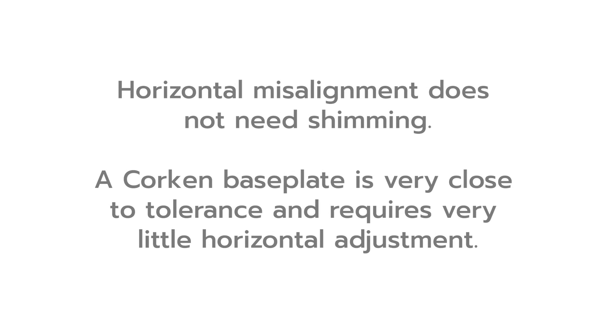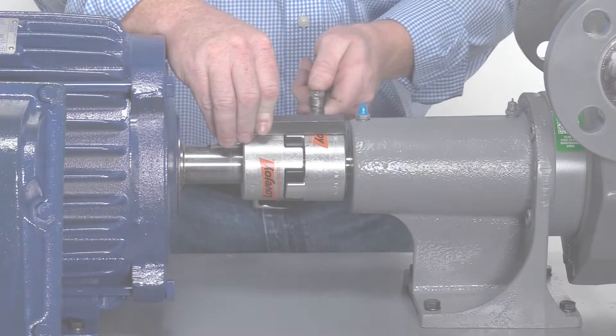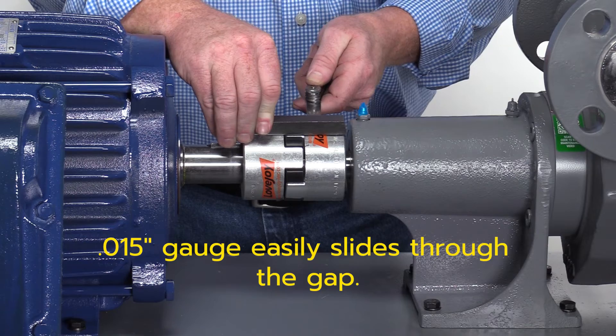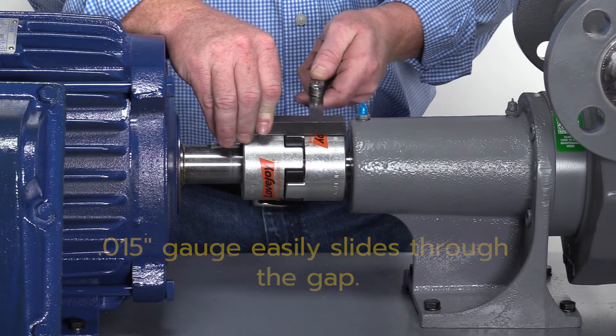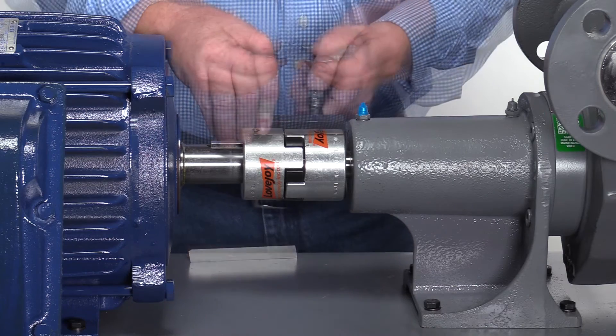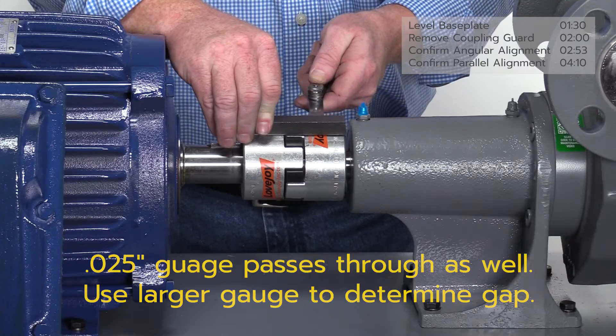Horizontal misalignment does not require shimming. A Corken supplied base plate is generally very close to tolerance and requires very little horizontal adjustment. Vertical misalignment requires shimming of either the pump or motor. In this example, the 15 thousandths gauge easily slides through the gap between the coupling and the straight edge. The coupling is out of tolerance and must be realigned. In this case, the pump shaft is lower than the motor shaft, so the pump must be shimmed.